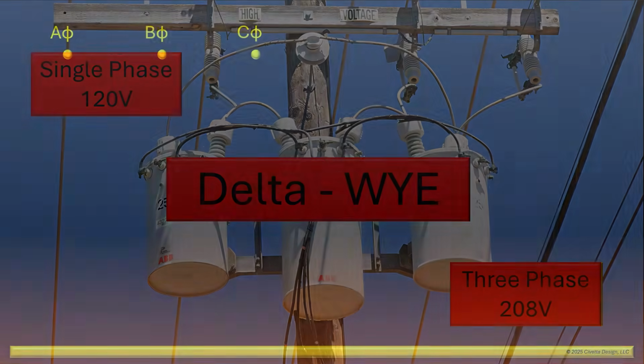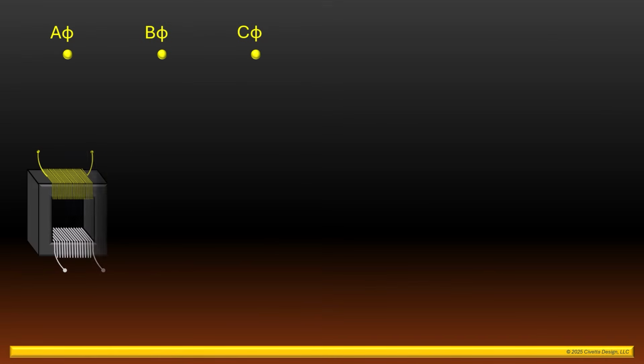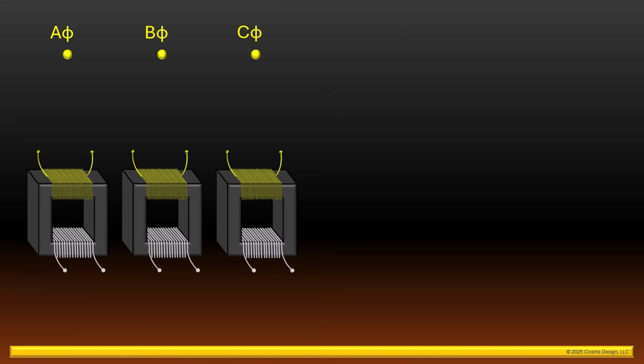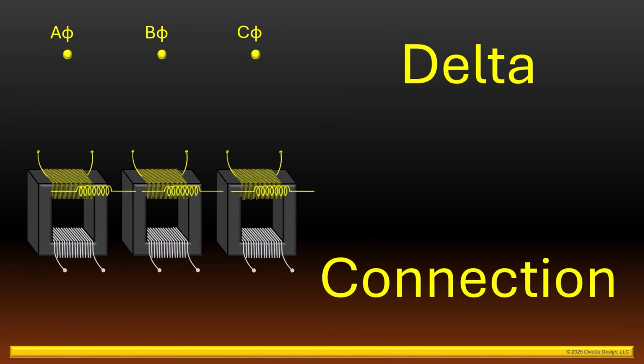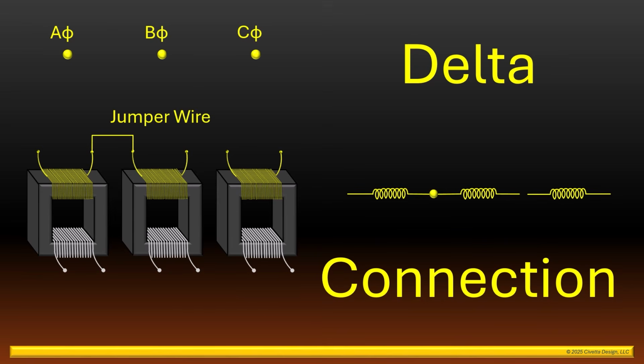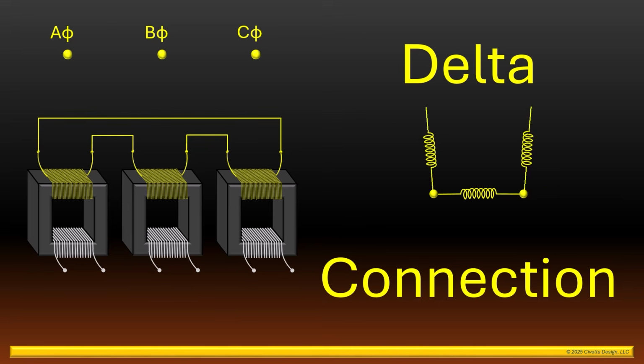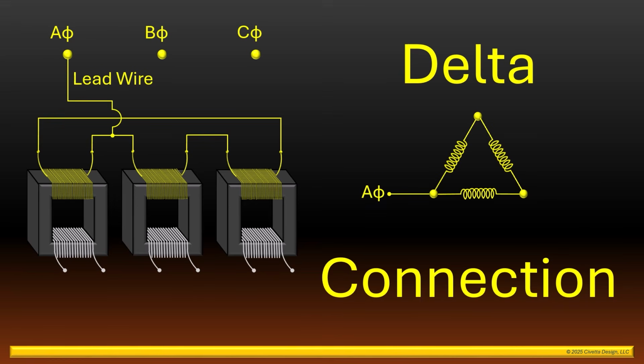Let's get to work. Since we want to use the same 12,000 volt transformers we used in the last video, we'll need to connect them to the primary system in a delta configuration, the same way we did last time. We'll start by connecting the 2 short jumper wires. The jumper on the left and then the jumper on the right. Then we'll connect the long jumper wire, which completes the delta configuration. We'll add the A phase lead, the C phase lead, and finally the B phase lead.